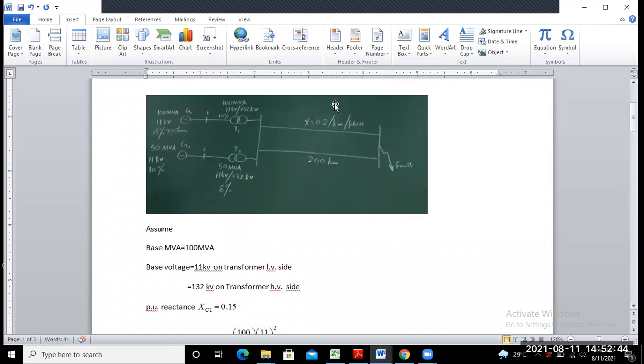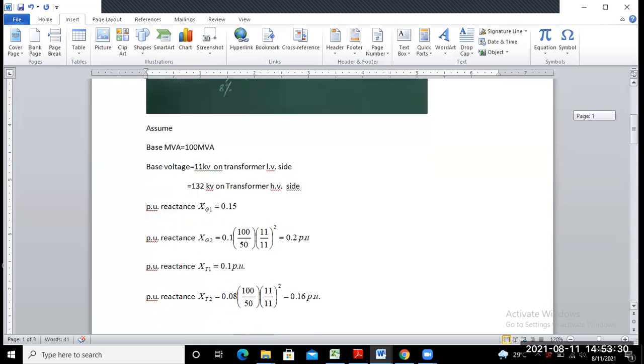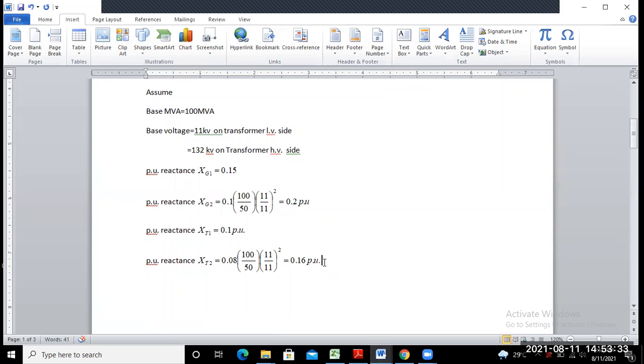So we already found the per unit reactance value of generator 1, generator 2, transformer 1, transformer 2. Now we just require to find out the per unit reactance value of this transmission line. So how we can find out the per unit reactance value of this transmission line? This value is given as 0.2 per kilometer per phase. So whatever the length, you have to just multiply here, then you will get the total reactance of the one transmission line, is it not, per phase? So 0.2 is your per kilometer, total length is your 200 kilometer. So just find out the value of x, that means of the transmission line, equal to how much? 0.2 into 200.